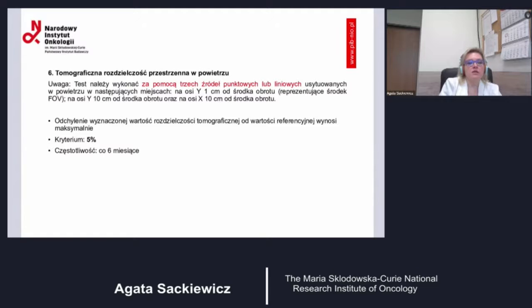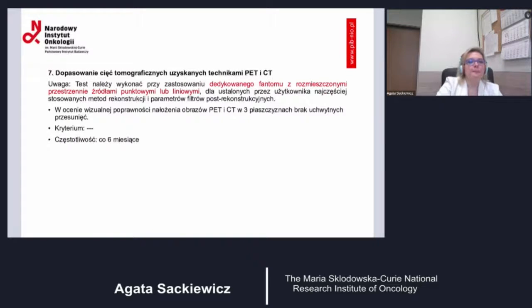Another test, which is done every 6 months, is the test of the tomographic resolution, spatial resolution in air, and it should be done using 3 point or line sources located in the air in specific locations, and the deviation of the tomographic value from the reference value can be 5% maximum. The seventh test is matching tomographic scans, PET and CT scans.